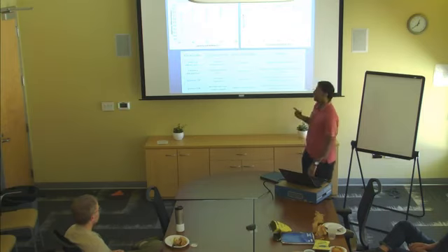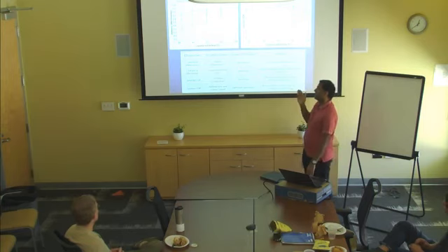They are not reduced significantly because we are keeping capacity and airflow rates synced, and as a result the duct inlet temperatures don't change. And as a result of that, even though the equipment COP actually goes up with reduction in capacity and airflow rates, which is the reason why variable speed systems are important, the system COP actually has some optimum points of operation.